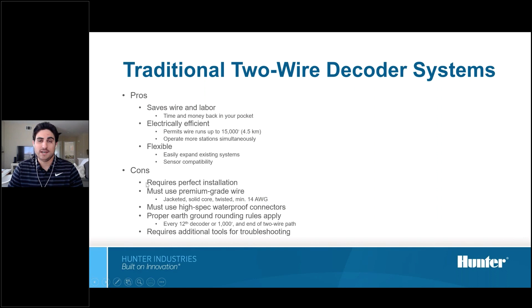So I would like to touch on some of the cons that we typically come across with a traditional two-wire decoder system, which ultimately posed the question for us to move into the EZDecoder system that we'll talk about moving forward. Some of the cons we tend to see with traditional two-wire decoder systems is you've got to have a perfect installation. You've got to have special twisted pair wire. You've got to have perfect wire connectors, those big DBRY6 silicone filled wire connectors that Kevin alluded to. Got to have perfect installation.